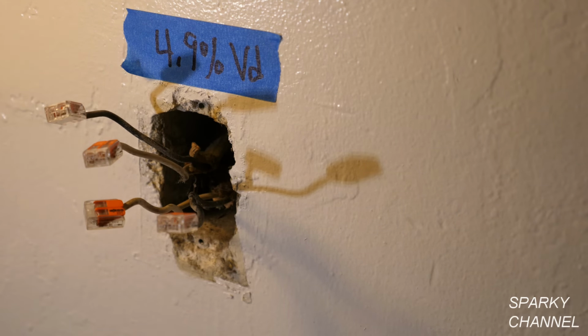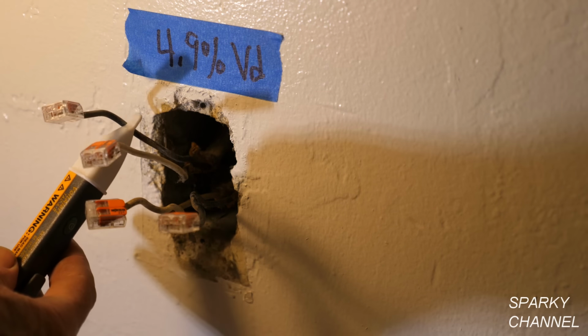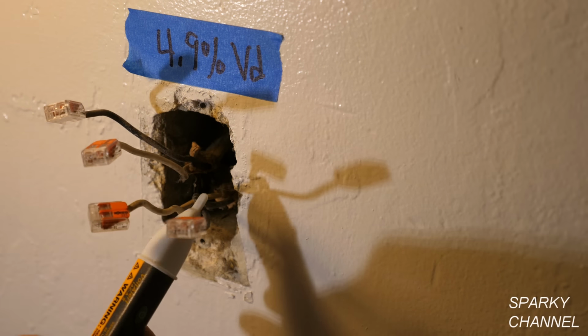So this is where I'm going to be putting the GFCI receptacle. So now I'm going to go turn off the circuit breaker. It's a very important step. You've got to remember to turn off the circuit breaker when you're working on it. I had to turn it on briefly to do this test, but then always remember to turn it back off. I turned off the circuit breaker, and you see nothing's live now.